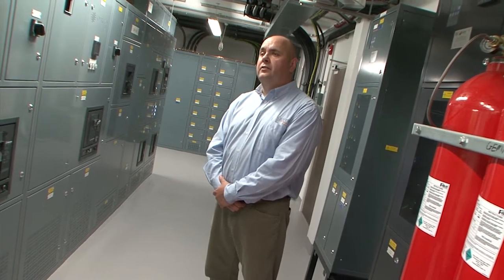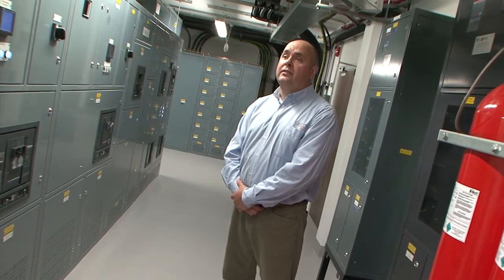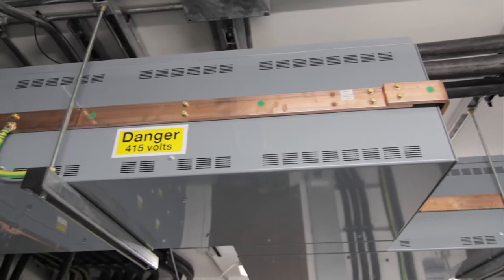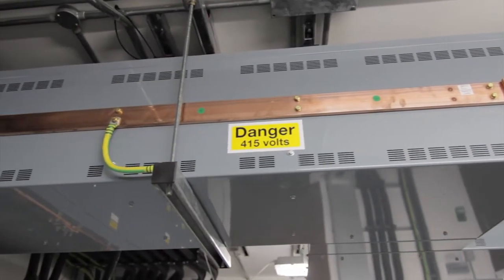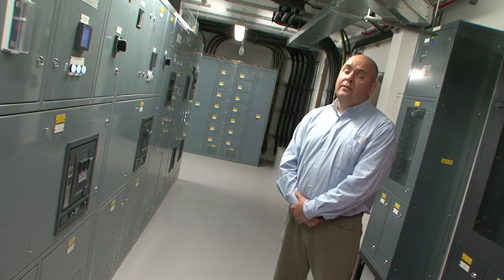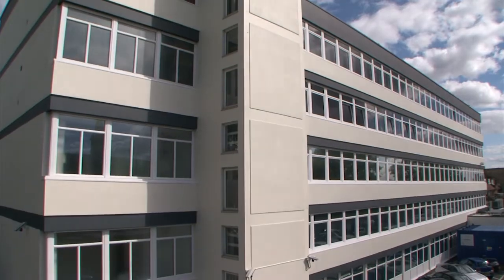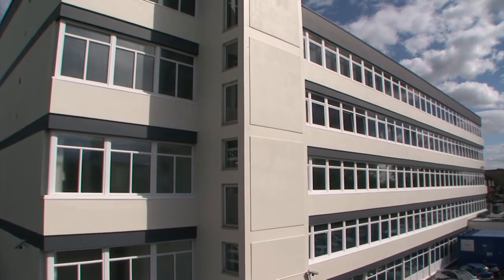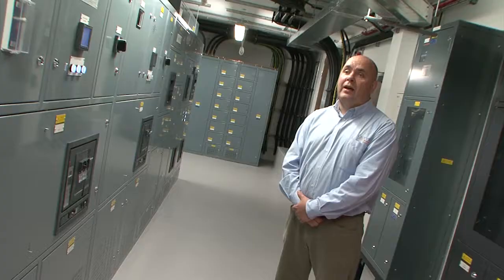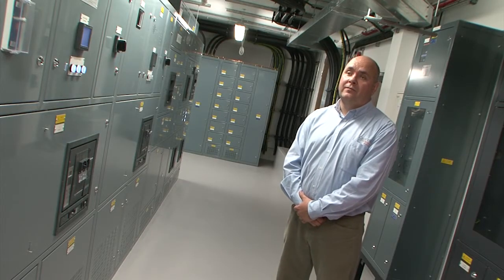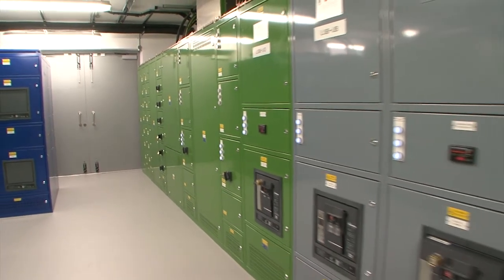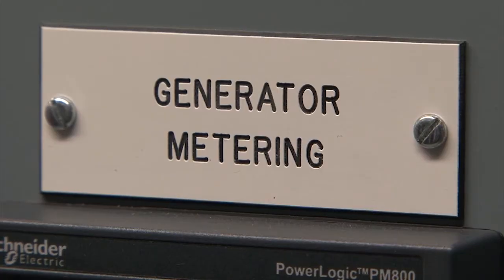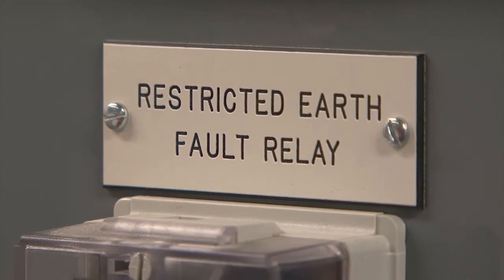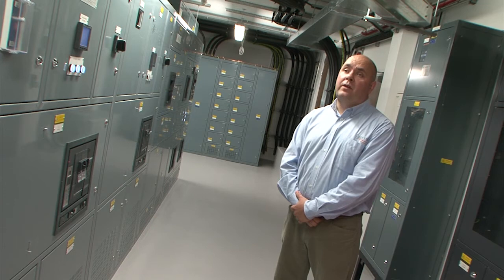One of the challenges to anybody looking to construct a data centre is the amount of raw power required to operate all the computer equipment. The added challenge to this building is the original construction was a 1960s build, with an incoming power of 300 amps per phase. The required power for this data centre is actually 3.5 MVA, and with the client we managed to design a system to give twin incoming streams, both capable of providing 3.5 MVA.